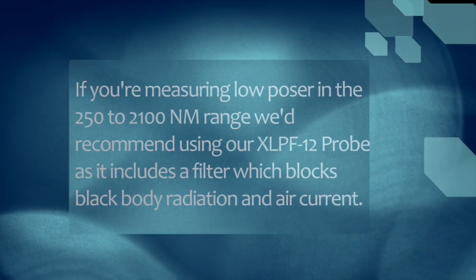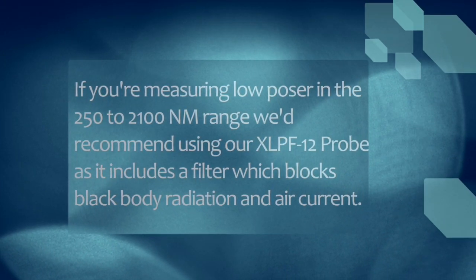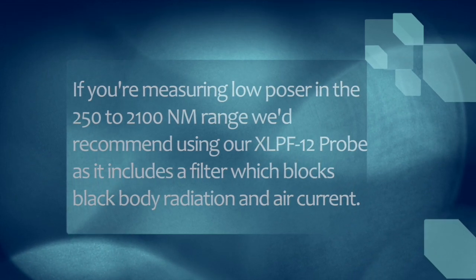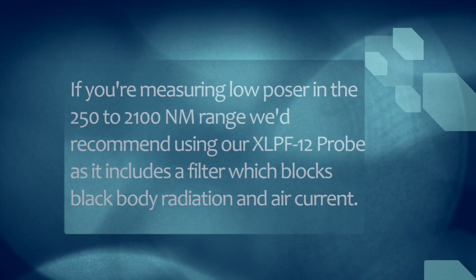If you're measuring low power in the 250 to 2100 nanometer range, we'd recommend using our XLPF-12 probe, as it includes a filter which blocks black body radiation and air current.